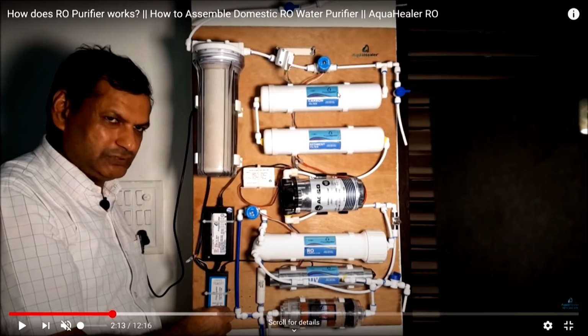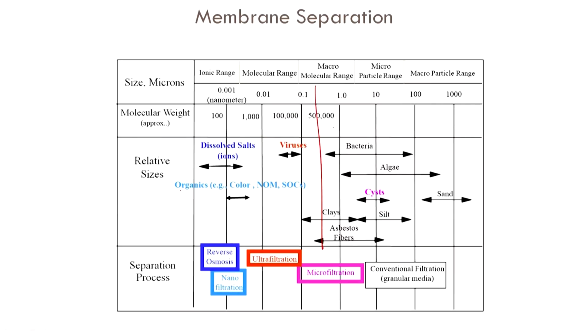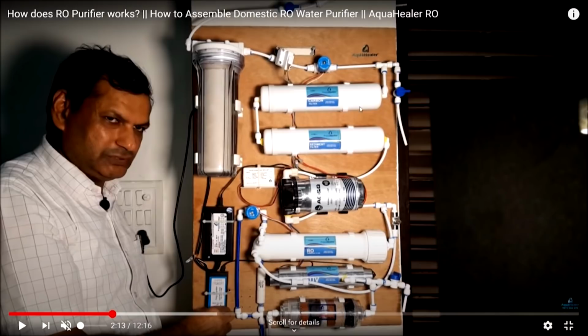The carbon filter, the activated carbon, is just for removing hydrophobic organic matter. So, where do we have that? You see some organics. It is not by size, but by change in phase. The hydrophobic organic matter will not want to stay in water. So, if you have activated carbon, it is going to adsorb onto the activated carbon, removing any organic content there. Typically in groundwater you would not expect any, but if there are any organic contaminants, they can be removed here. Again, activated carbon is pretty cheap.